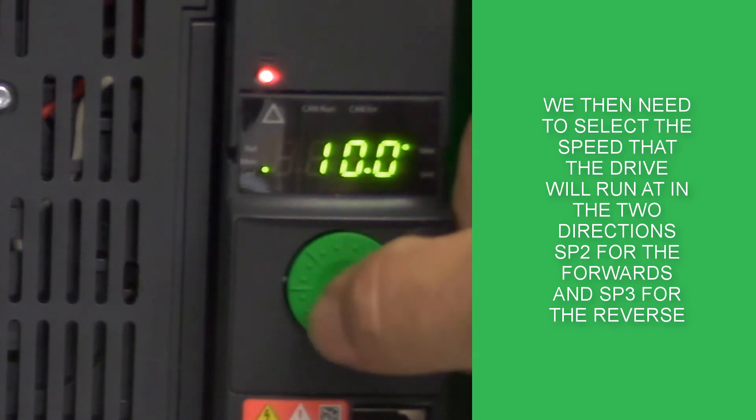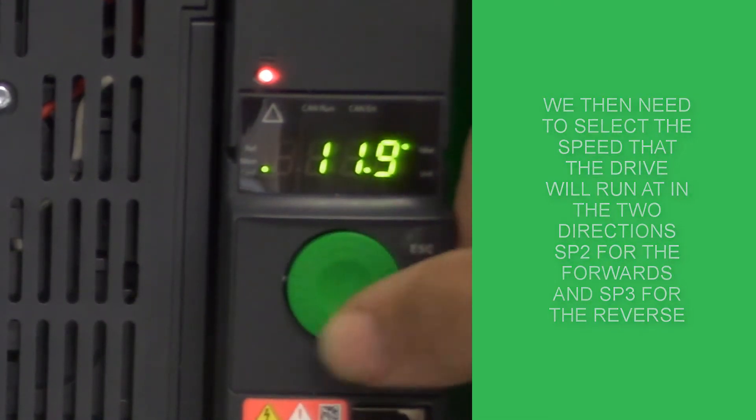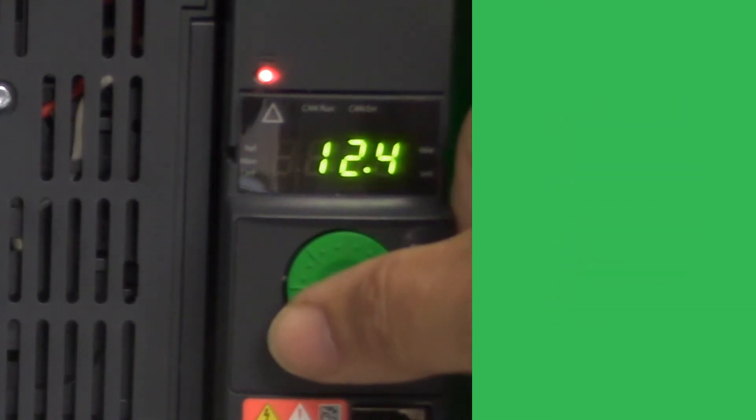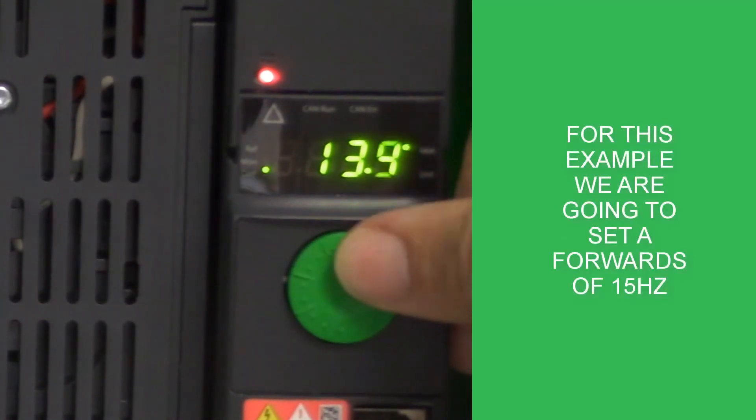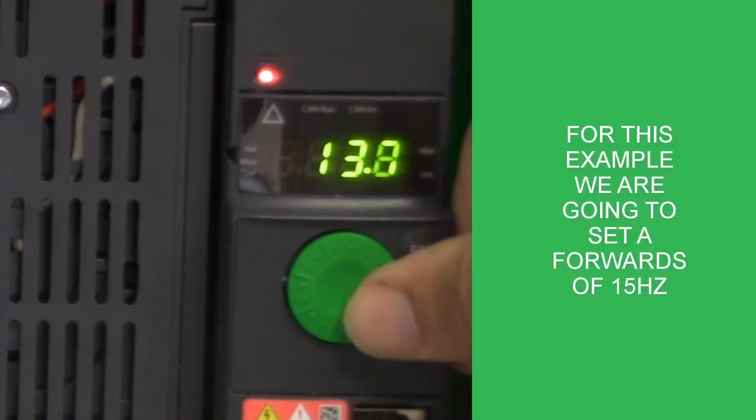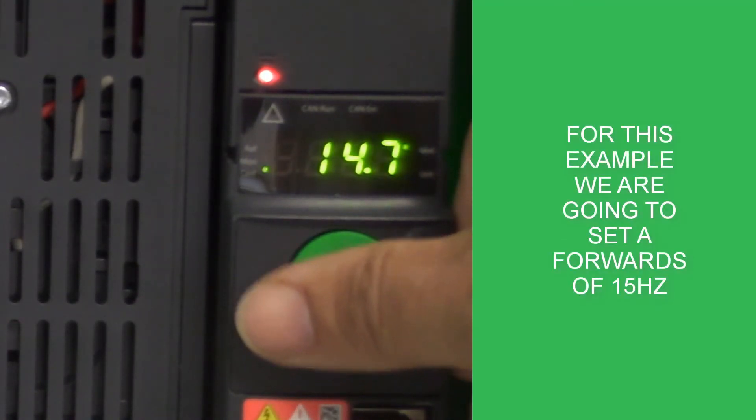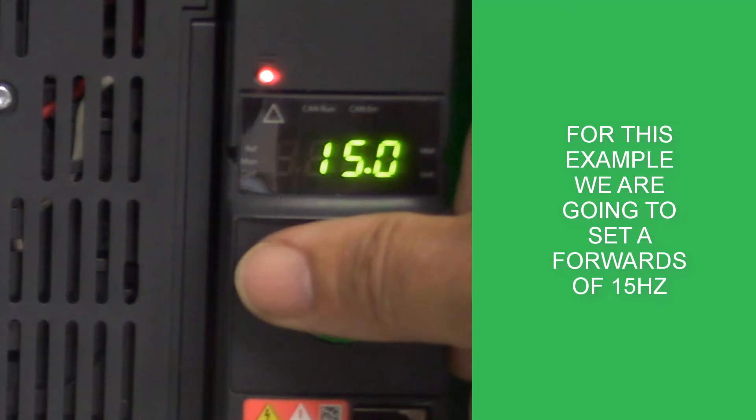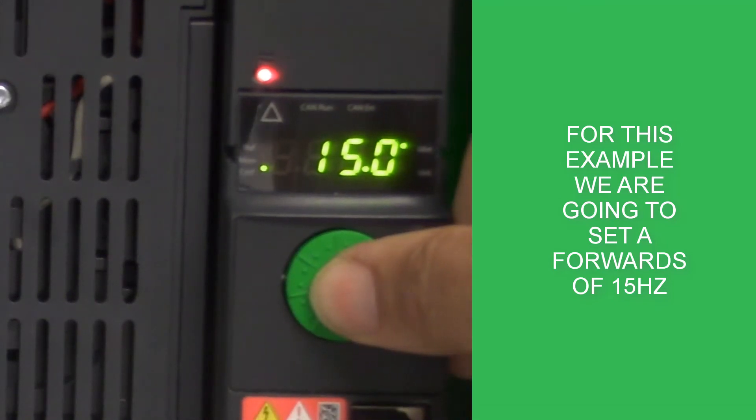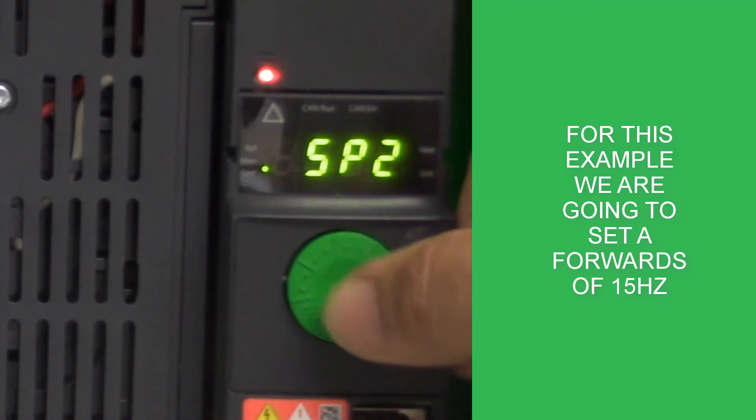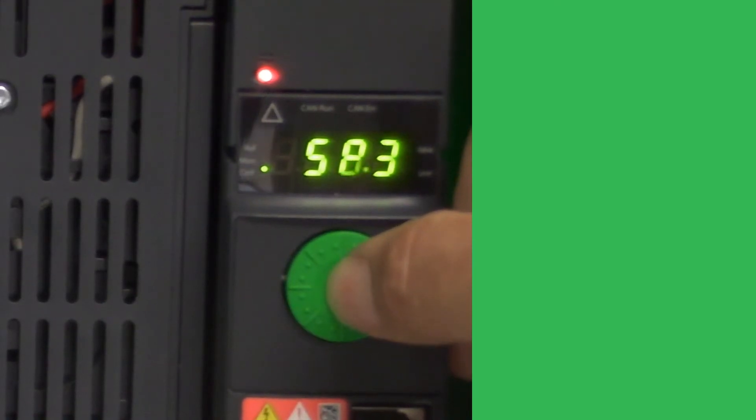We do this by assigning our preset speed 2 to our 15Hz for our forward direction. Once we've set this, we go to SP3, preset speed 3, and assign that to our reverse speed of 35Hz.